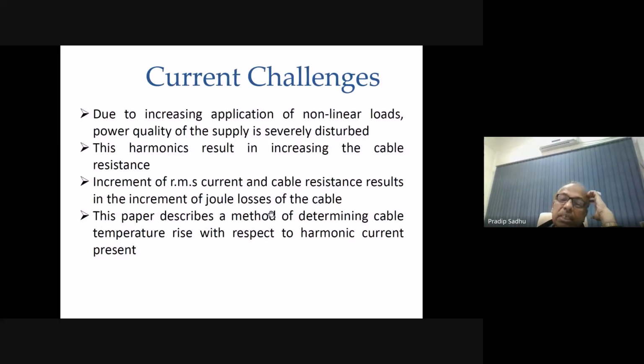The current challenge is that due to the increasing application of non-linear loads, the power quality of the supply is severely disturbed, and these harmonics increase the cable resistance. We know this from harmonic analysis: which harmonic orders are present along with the fundamental component. If the third and fifth order harmonics are large, then at higher frequency the cable is almost short-circuited, as XC is 1/(2 pi FC). Higher order harmonics create a leakage path for the current, and cable heating will be much more for that reason.